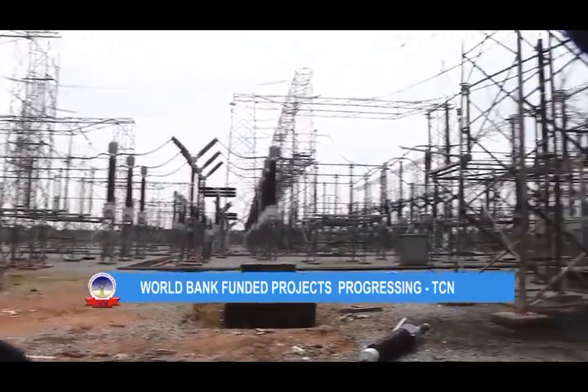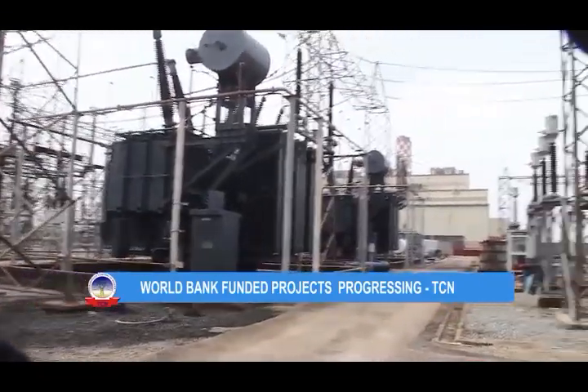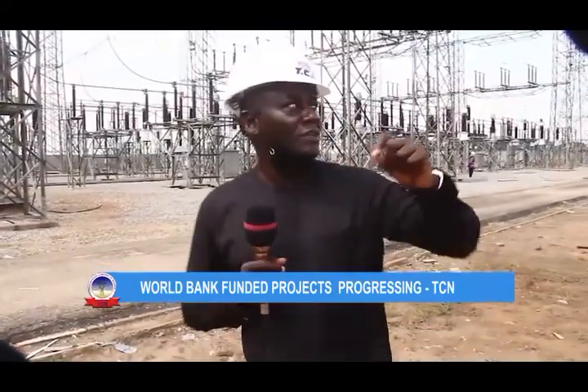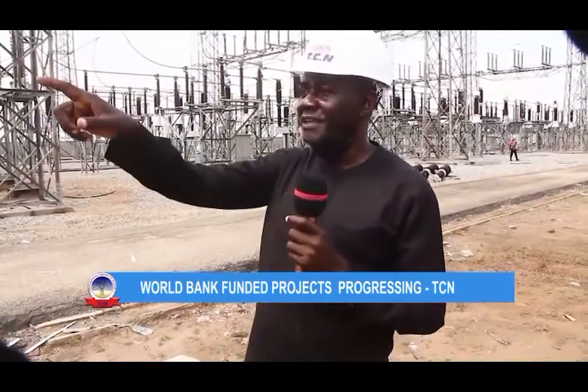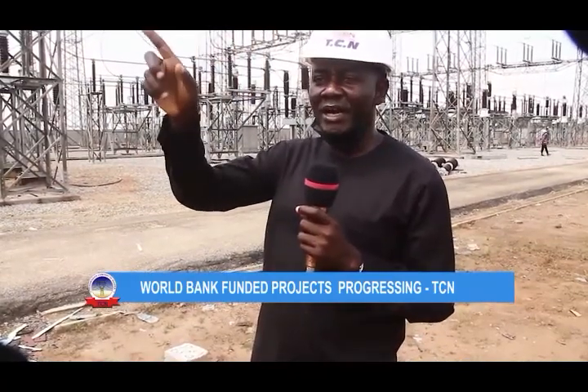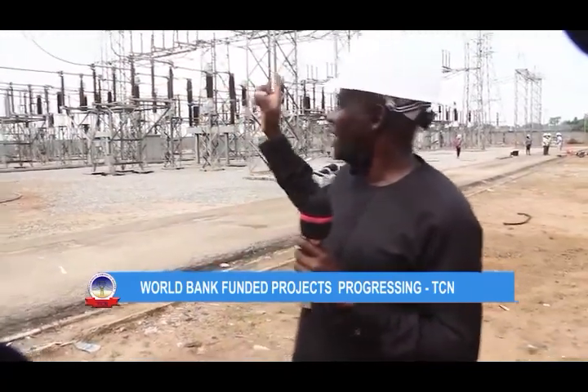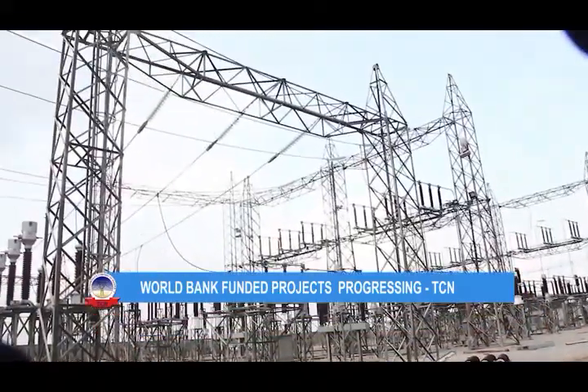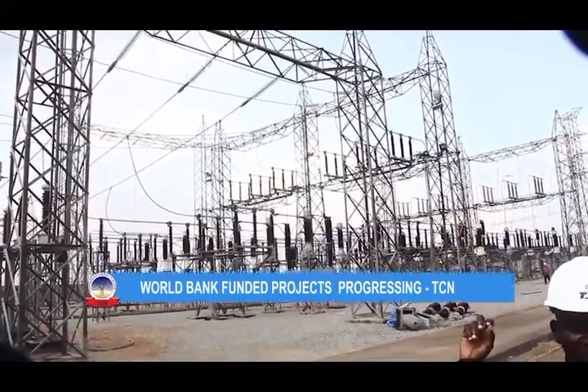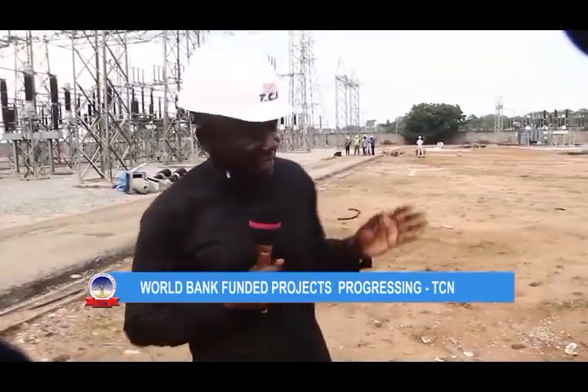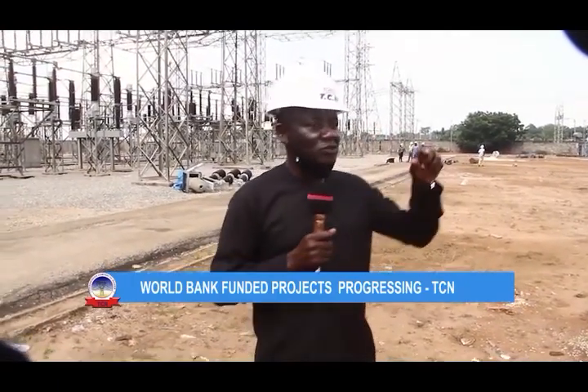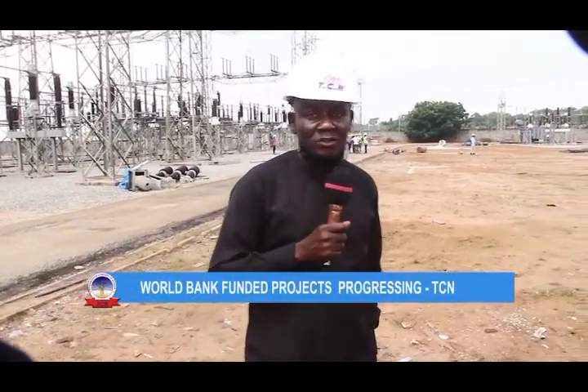By the time we finish this rehabilitation exercise and improve the transformer bay, with extension of the bus bar system - we currently have a 330 kV bus bar arrangement, a 1.5 circuit breaker system, and a double bus bar called bus bar north and bus bar south. Management is looking at extending this bus bar to accommodate another 300 MVA power transformer. This will increase our capacity to wheel out more power to the general public, to Lagos State and Oyo State in general.